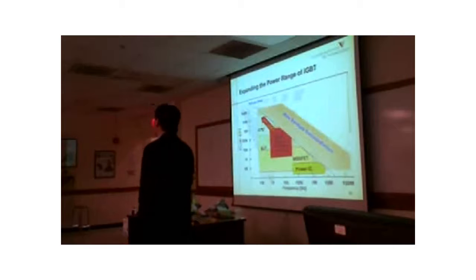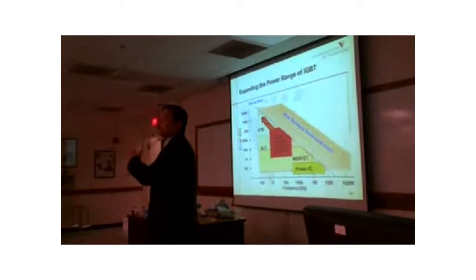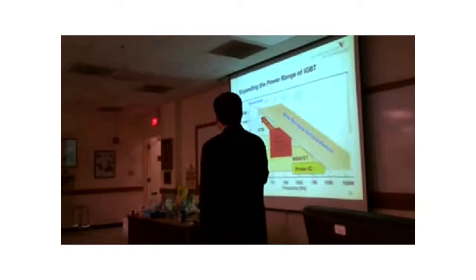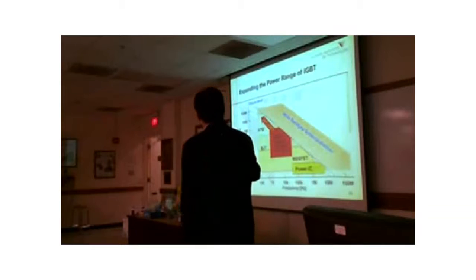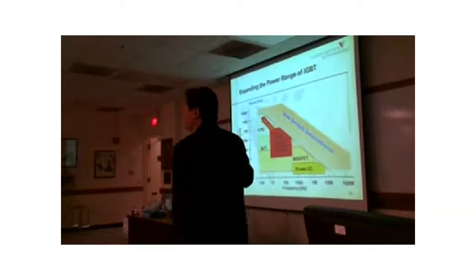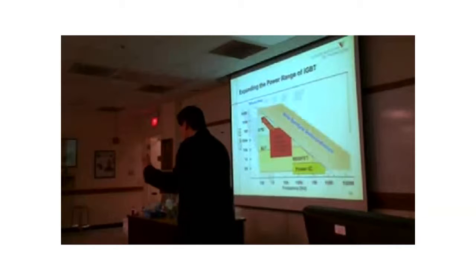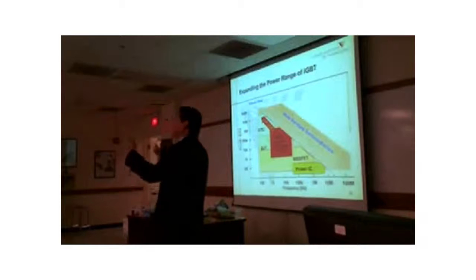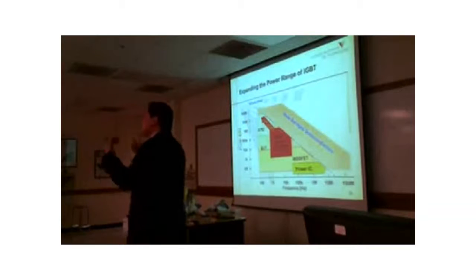Because at a couple of megawatts, people do not tend to switch those that fast. For one thing, the switching loss will be high. For the other, there's not a whole lot of need to switch it so fast. Especially with multi-level converters, the equivalent output frequency will always be higher than the individual stages' switching frequencies. For each individual switching stage, maybe 1 kilohertz, maybe 500 hertz is all you need. But the beauty of using IGBT instead of GTO is, some papers did a comparison between GTO and IGBT in high power applications. Basically, the conduction loss and switching loss are about the same.